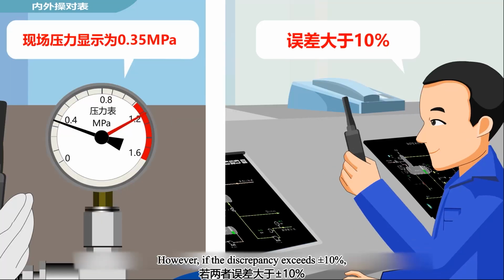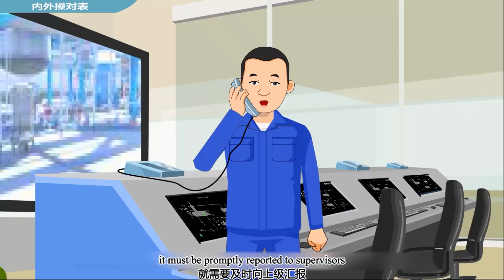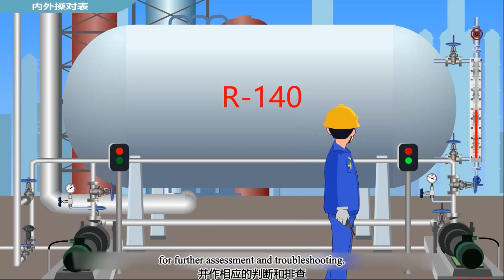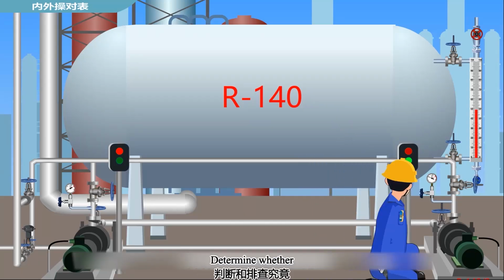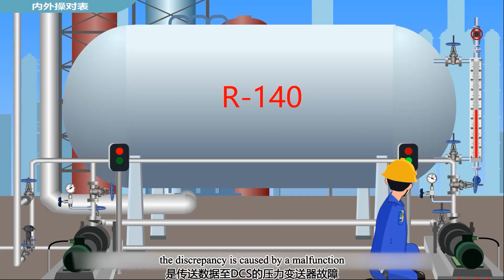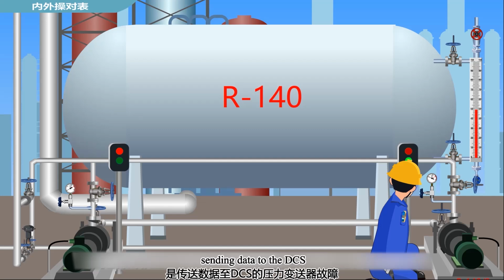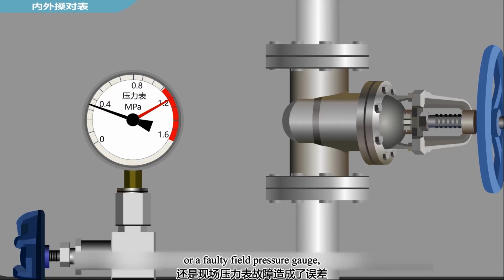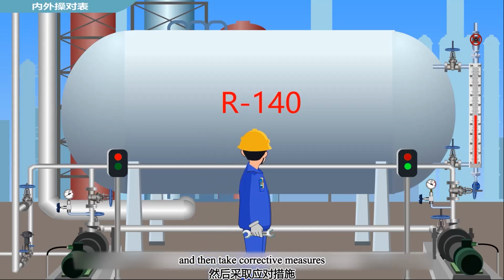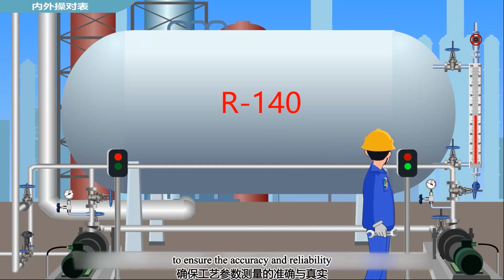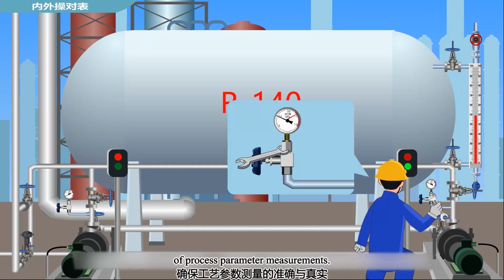However, if the discrepancy exceeds plus or minus 10%, it must be promptly reported to supervisors for further assessment and troubleshooting. Determine whether the discrepancy is caused by a malfunction of the pressure transmitter sending data to the DCS, or a faulty field pressure gauge, and then take corrective measures to ensure the accuracy and reliability of process parameter measurements.